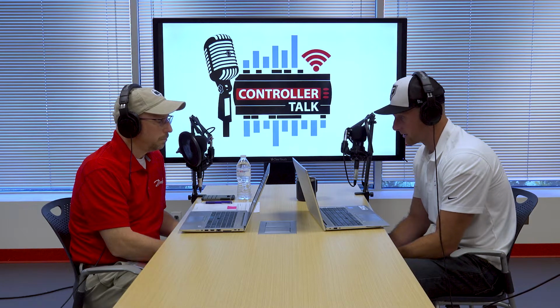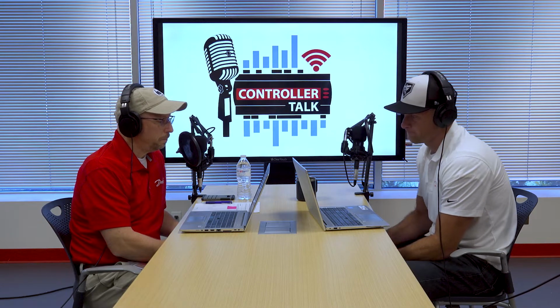And so that's option 2. When you're in the rack controller, in your heat reclaim section, when you set the type for HVAC, there's an option for board and point. And that would be the choice that I just described. Yep. And in that rack control, there's another option that some people still use. It's called the heat reclaim flush. Mm-hmm. And that's been around for a long time. But some people do use it because they feel like oil can get kind of stuck in that heat reclaim coil.